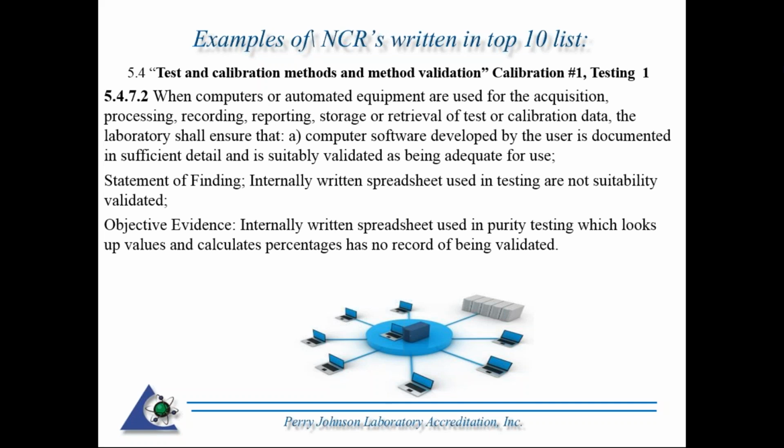So 5.4.7.2, and I come across this on some of my assessments, and there's a little bit of confusion with this. I find this has got to do with software validation. So the requirement states, when computers or automatic equipment are used for the acquisition, processing, recording, reporting, storage, and retrieval of test and or calibration data, the laboratory shall ensure that computer software developed by the user is documented in sufficient detail and is suitably validated as being adequate for use.